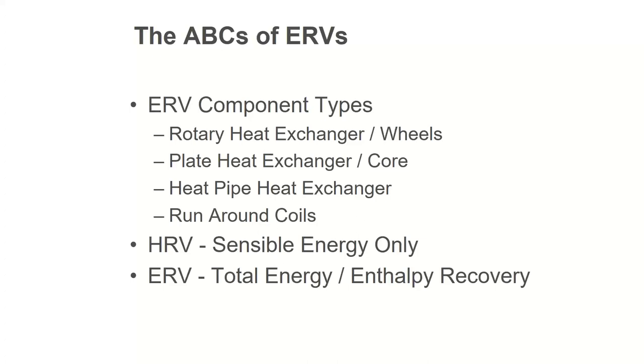So, different types of ERVs. I mentioned wheels. There's also fixed plates. I don't know if you've seen those. Two plates crisscross each other and we exchange heat that way. There's heat pipes, runaround coils. There's different styles out there. Heat pipes and runaround coils are not going to help us comply with the code requirements because they can't do latent recovery. Wheels and cores can be done in a latent or non-latent version. You would need the latent version, the enthalpic core, enthalpic wheel, in order to be able to comply with code.